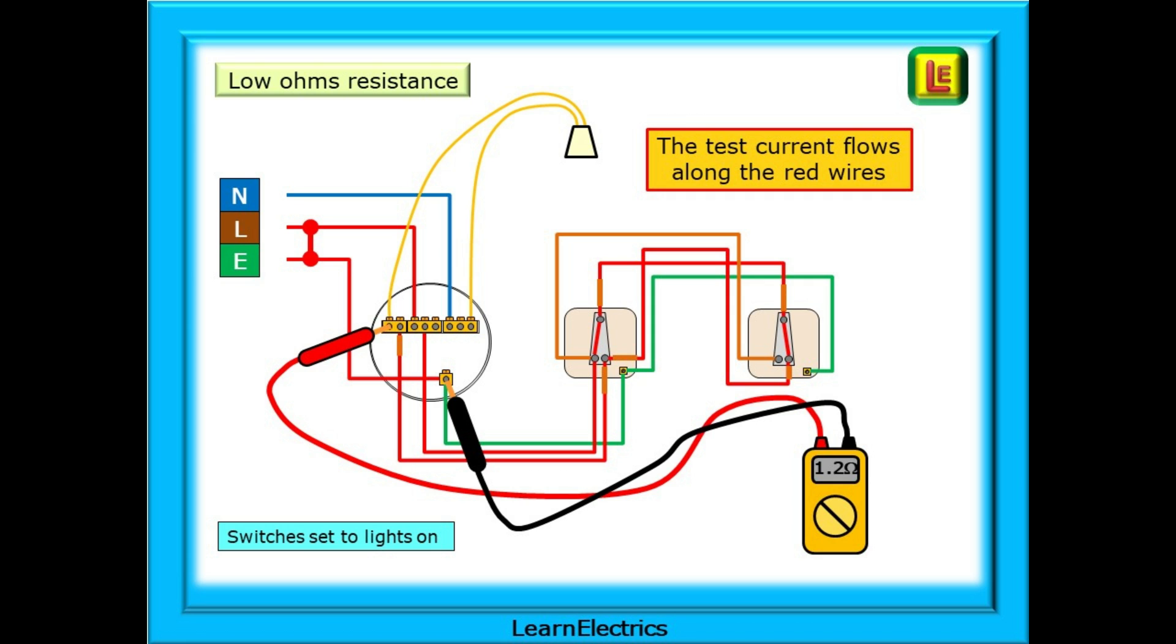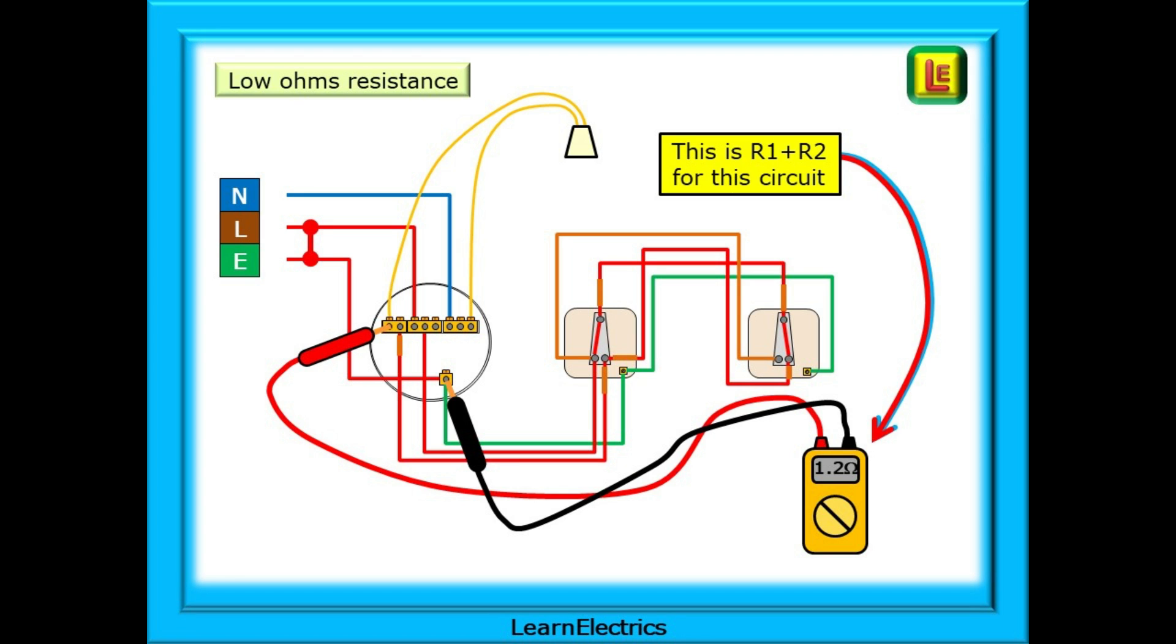You should have a low ohms reading of just one or two ohms or so. Any reading above five ohms is an incorrect reading. If your meter reads the maximum, 299 ohms or 999 ohms, OL or similar, then this usually indicates that one of the switches are set to lights off. Simply operate just one of the switches and this should now test OK. This reading, 1.2 ohms as shown here, is the R1 plus R2 for this circuit and can be recorded on the test certificate.